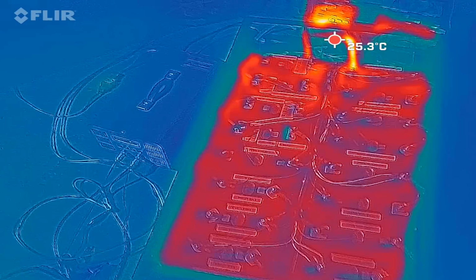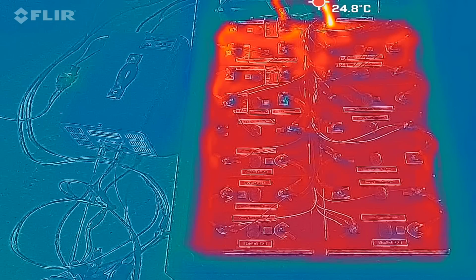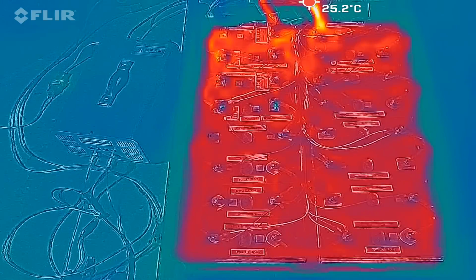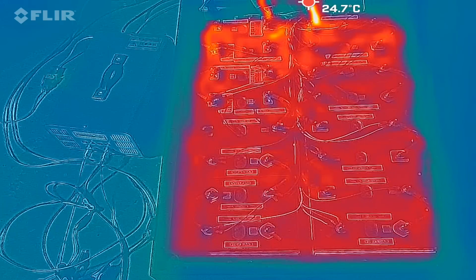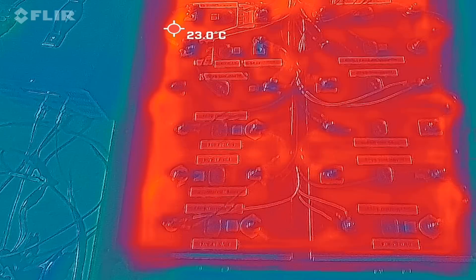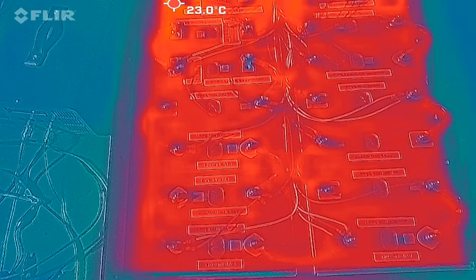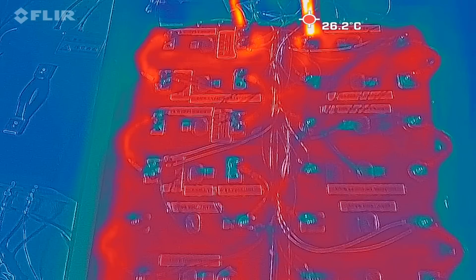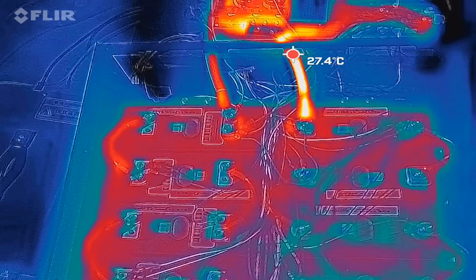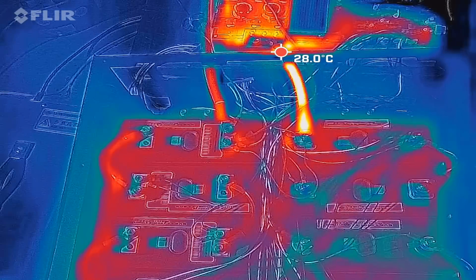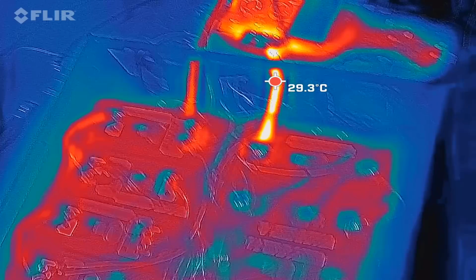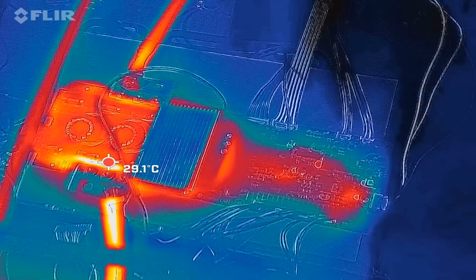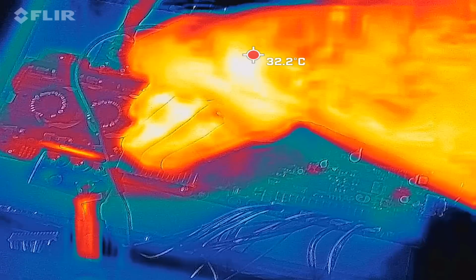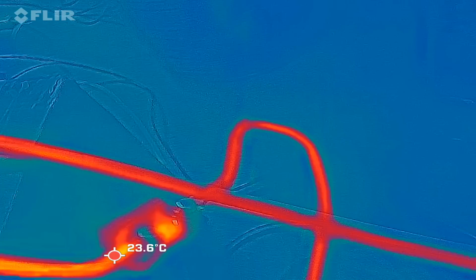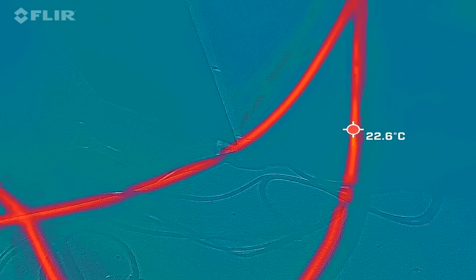So we've now charged for a bit over an hour, and we're down to 73%. I'm doing another check here with the infrared camera, but the battery looks fantastic, very uniform. No big hotspot—there's one cable there at 27 degrees, but I'm not considering this a hotspot. The BMS doesn't get hot, nothing. Smart shunt, cables, all good.